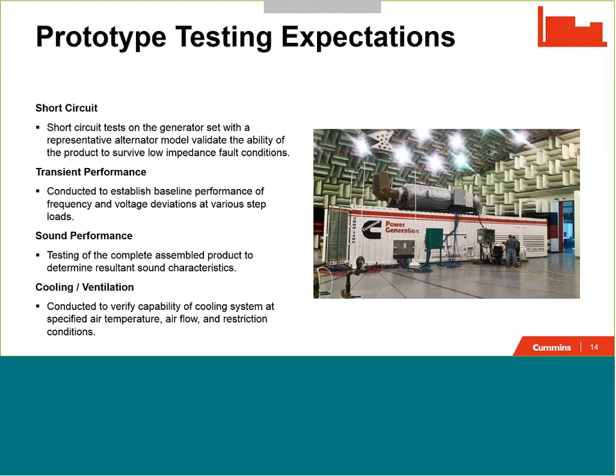Sound performance is another key piece here, where we see sound testing being conducted as a prototype. However, it also needs to be tested later on at the site in order to validate performance. Sound testing is often challenging for generator set manufacturers, especially for high horsepower products. What you're seeing there on the right picture and in the picture early on, that facility is specifically designed to absorb all of the sound that is transmitted or propagated through the structure from the generator set. A manufacturer that is using an engine test cell or a small generator set test cell to conduct sound testing may not be able to deliver quality sound data during their prototype test, which may result in a product that once installed on site may not meet your local requirements for sound, and that can be obviously a concern or a challenge that you or the owner has to manage.